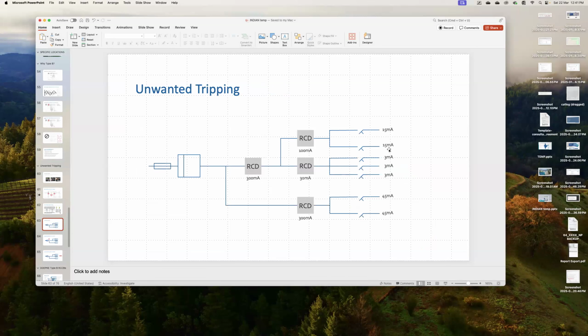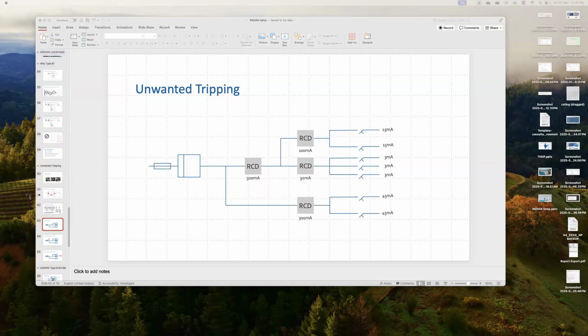When we individually checked the flats, we found there was some leakage current, and because of that it is exceeding that 30 milliamps and getting tripped. Our question was why a few apartments, 10 apartments, are getting tripped simultaneously. Is there anything connected to the input source? Most cases, you can unshare.